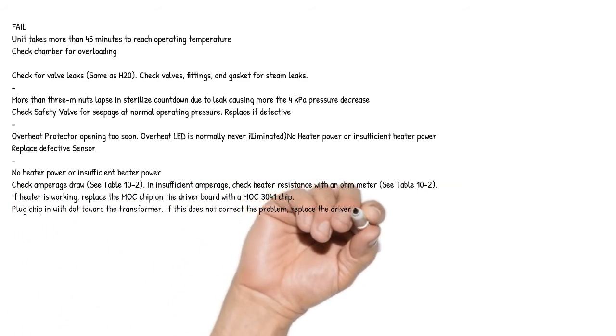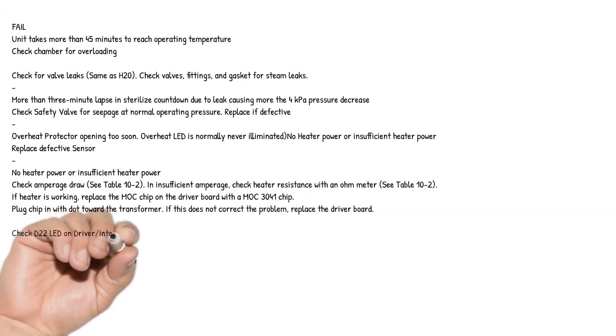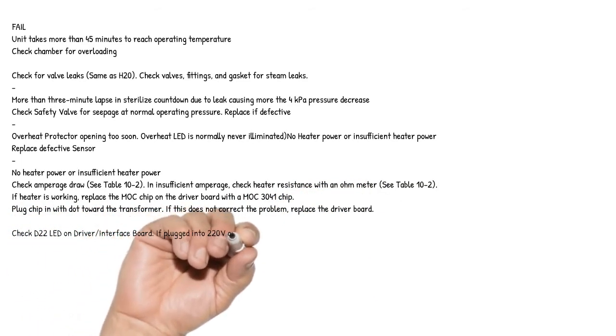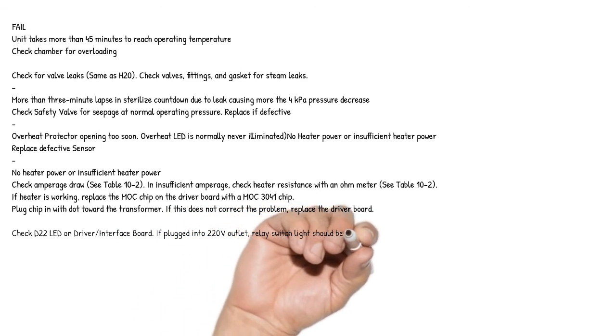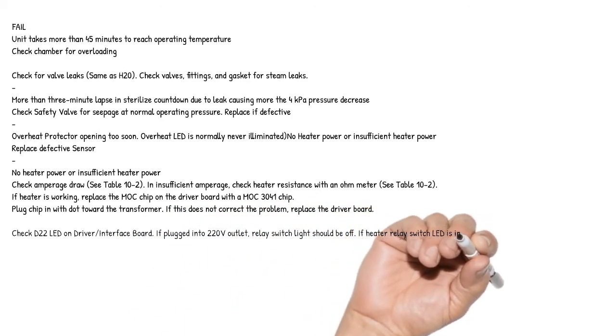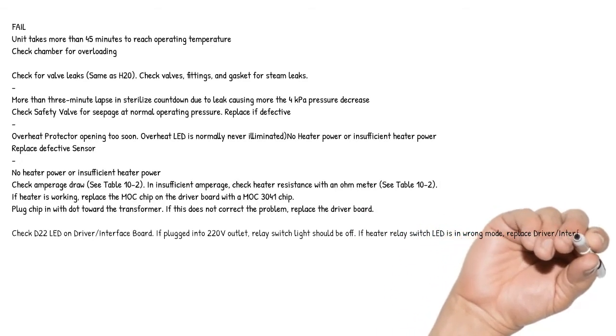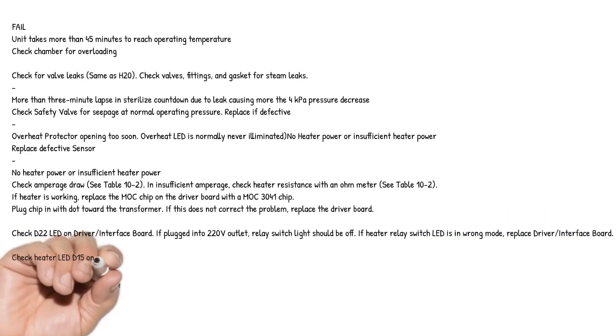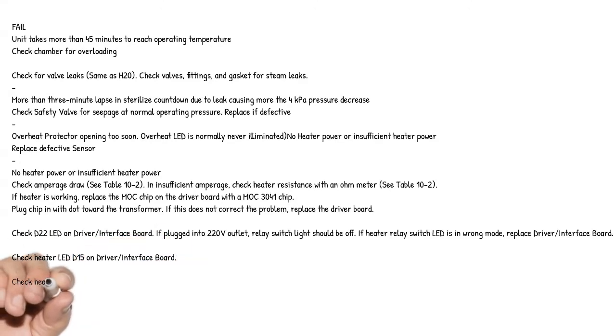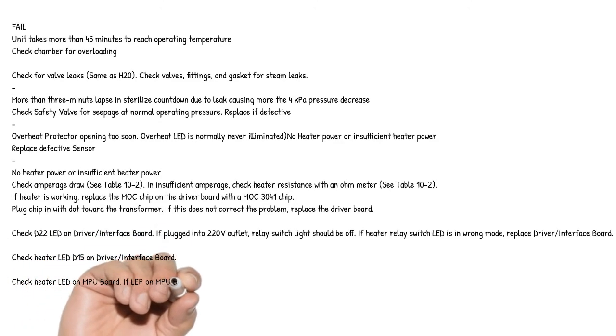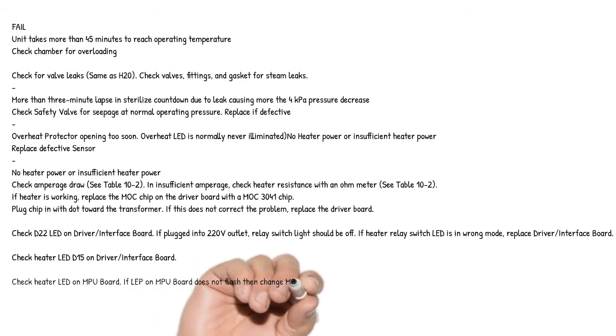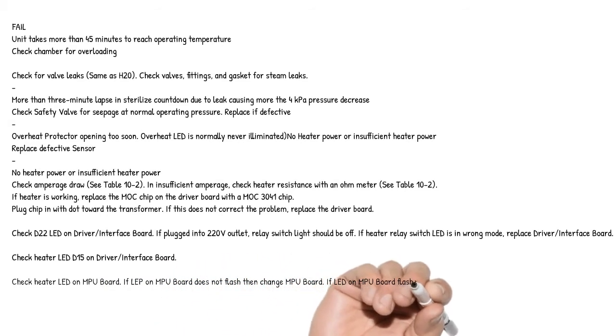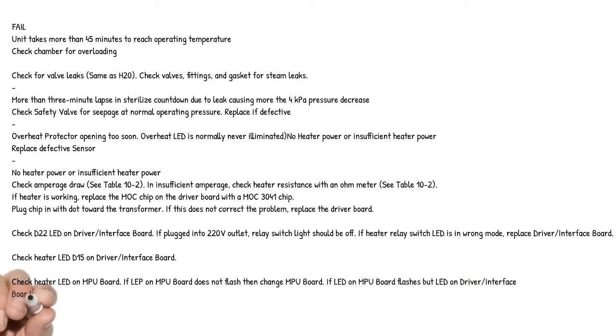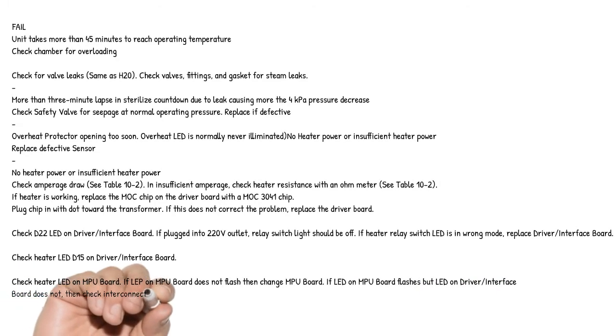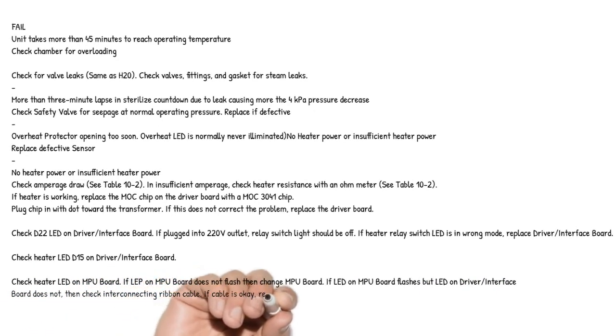Check D22 LED on driver/interface board. If plugged into 220 volts outlet, relay switch light should be off. If heater relay switch LED is in wrong mode, replace driver/interface board. Check heater LED D15 on driver/interface board. Check heater LED on MPU board. If LED on MPU board does not flash, then change MPU board. If LED on MPU board flashes but LED on driver/interface board does not, then check interconnecting ribbon cable. If cable is okay, replace driver/interface board.